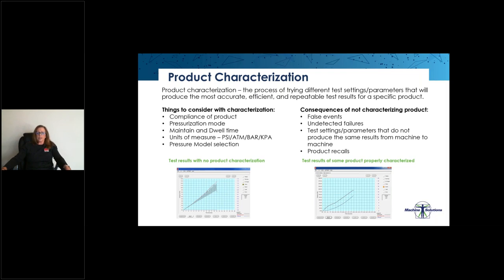Pressure manager is a great tool for doing product characterization. It allows us to see the pressure and volume graph in real time. And with sensitive enough settings, we're able to dial in the correct compliance and burst and leak criteria in order to get the repeatable results that we're after.